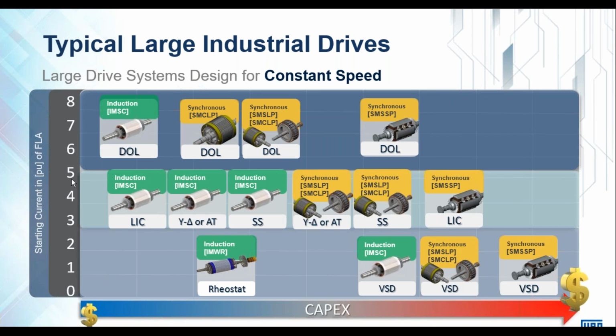Okay, then in the medium impact zone, of course, we can use standard induction motors coupled with indirect starting methods such as reduced voltage starters, either star delta starters or soft starters. Another option, which we're going to examine in a little bit more detail shortly, is this low inrush current design motor without any additional starting hardware attached. It is just an adaptation of the design of the machine to enable us to reduce the starting current.